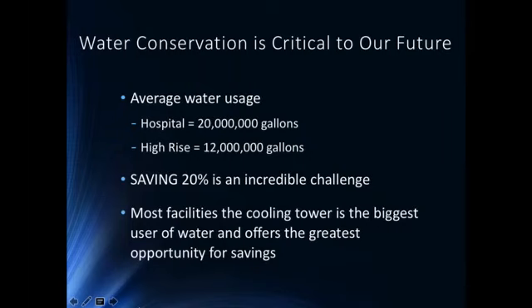And when you start talking about, and again, these are just averages because they can go up way higher than this, but through the cooling tower system, the average hospital uses about 20 million gallons. The average high-rise in some areas can use as much as 12 million gallons. And again, they can be much, much higher than this depending on the heat load and the size of the building. Saving 20%, as Maureen mentioned earlier, is an aggressive goal, but also an incredible challenge, but one that needs to be tackled both from a sustainability and a saving money standpoint.